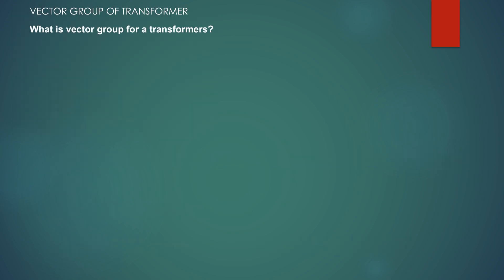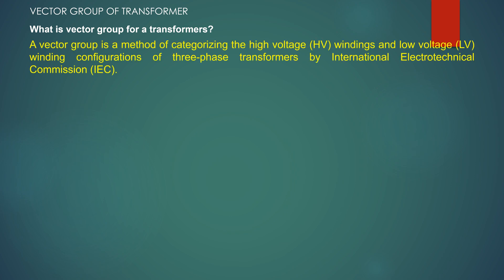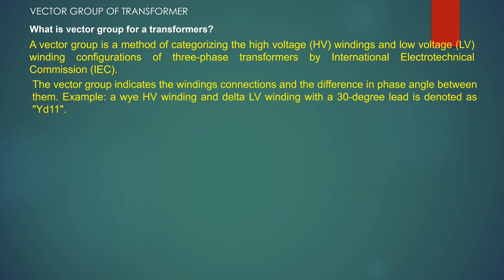A vector group is a method of categorizing the high voltage winding and low voltage winding configurations of a three-phase transformer, defined by the International Electrotechnical Commission (IEC). The vector group indicates the windings connection and the difference in phase angle between them. For example, a star HV winding and a delta LV winding with a 30-degree lead is denoted as YD11.